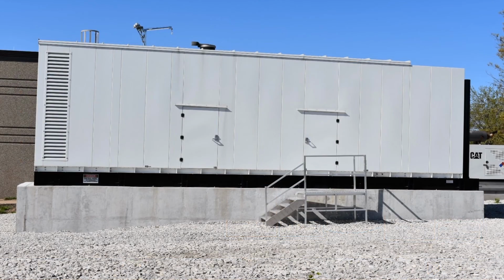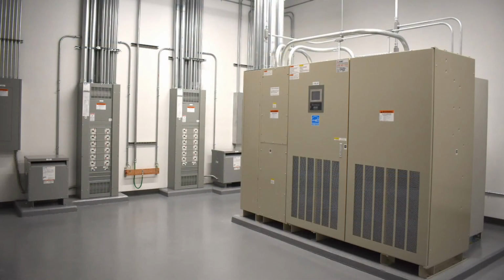The generators are housed in an equipment yard on the south side of Building 1. Upon expansion, the equipment yard will be centered between the two buildings. Each generator is 1.5 megawatts and an N+1 configuration. The facility utilizes 2N UPS design, providing both an A-side primary power feed and a B-side redundant power feed to each customer cabinet. Neither side is loaded beyond 40%, allowing for complete load to be handled by either side independently. Our power systems are designed to provide both fault tolerance and concurrent maintainability.